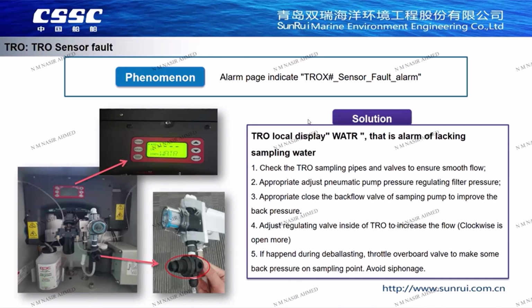Next is the TRO sensor fault alarm. There are two most common alarms. One, the TRO cannot take water normally. The WATR alarm code will be displayed locally on the TRO. In case of this fault, first check the TRO water intake pipe. Confirm whether the sampling pump in the TSU can take water normally. If the sampling pump can take water but the TRO has no sampling water, the backflow valve along the TRO sampling line can be properly closed to increase the TRO inlet back pressure. Secondly, the black regulating valve inside the TRO can be adjusted. Check whether it was closed by faulty operation. The valve regulating is reversed, opening clockwise and closing counterclockwise.